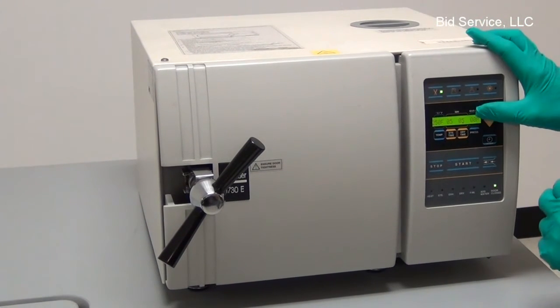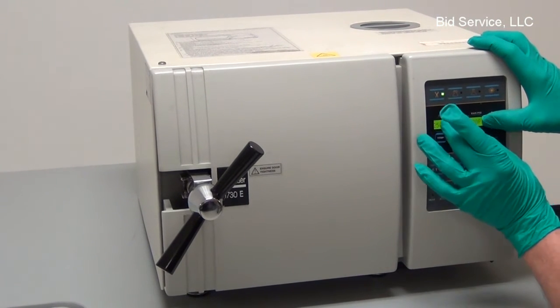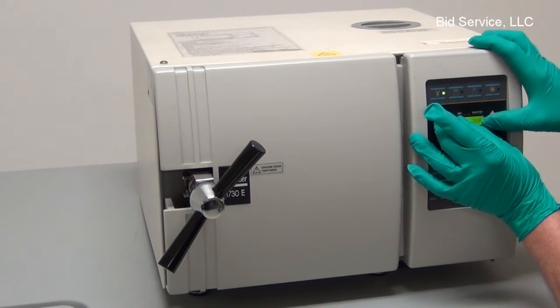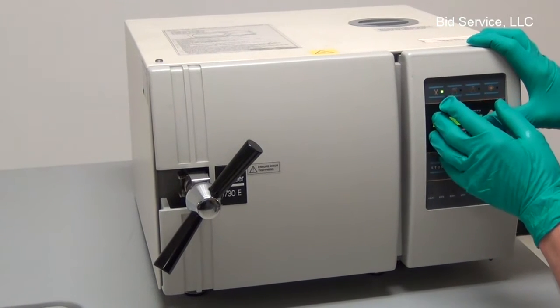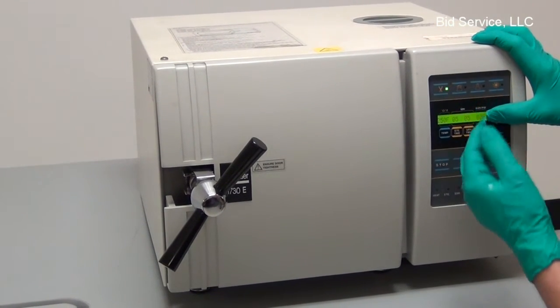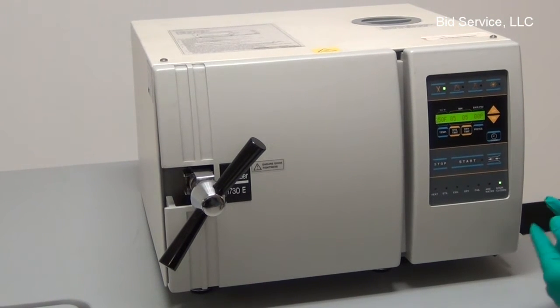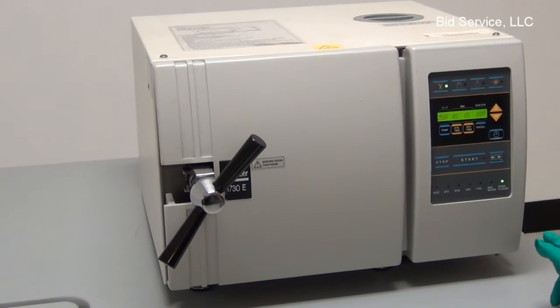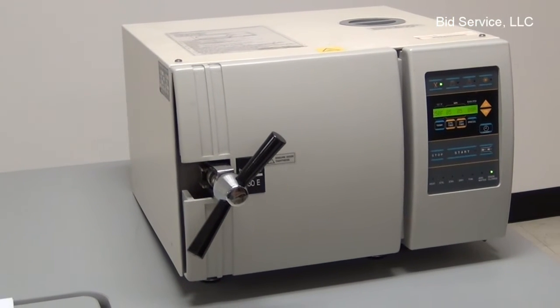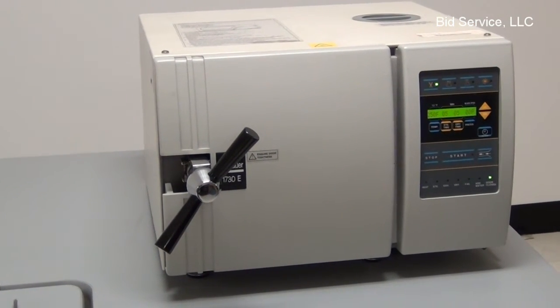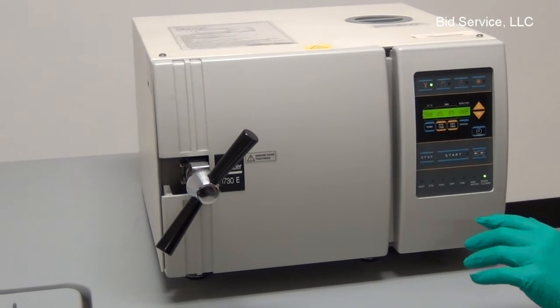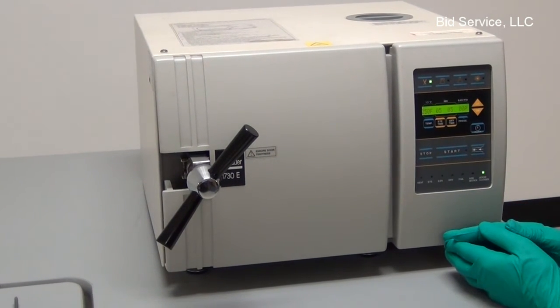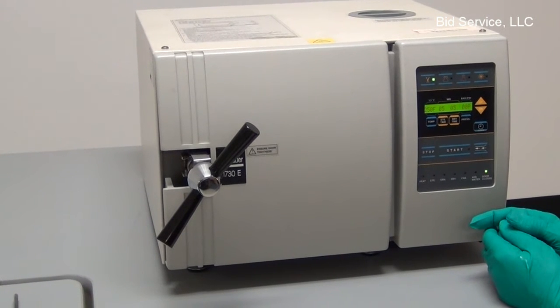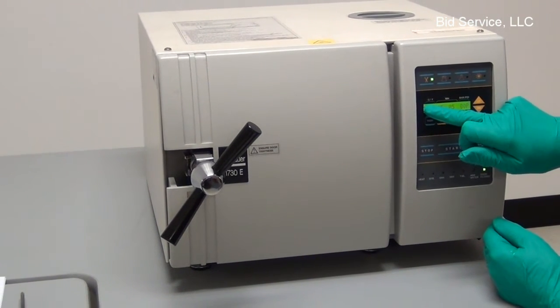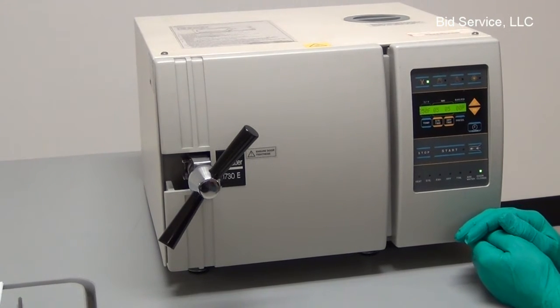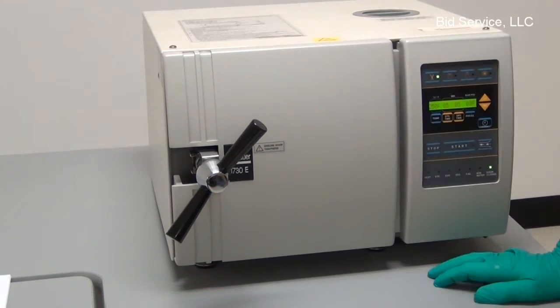For example, if the pressure should be too low, you will get an error display here that will say your pressure is too low. If your pressure is too high, the same thing will occur. It also monitors low temperature and high temperature as well. If, for example, you get a low heat indication, this one's important to remember because the most common one that you might see is low heat. And that would point to something that normally you would maintain.